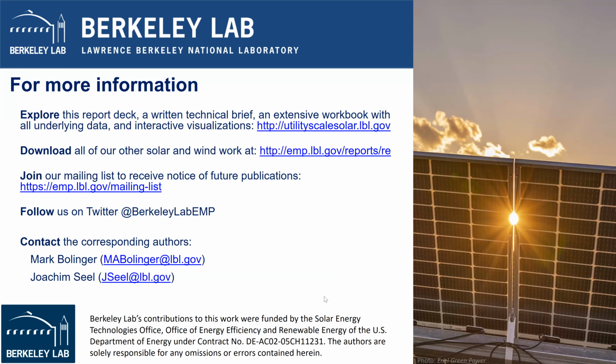Similarly, there was a question, how does this then manifest in price differences? Well, if you express it in DC watt terms, and your DC wattage is bigger because you have more modules relative to the inverter capacity, then the denominator is larger, and so the resulting price is a little lower. If you express it in AC terms, and you have a fixed inverter but add more and more modules, your price is going to increase, while your denominator is not growing with that, and so that then yields higher dollars per watt AC cost numbers.